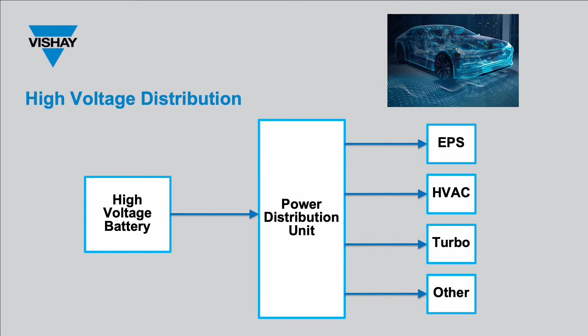In a new reference design by Vishay, an eFuse has been designed to handle continuous power up to 40 kilowatts. It can operate at full power with less than 30 watts of total losses and no active cooling, and also features a pre-charge function, continuous current monitoring, and overcurrent protection, with complete shutdown in less than 2.5 microseconds.